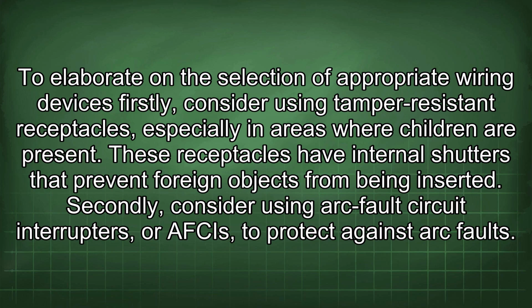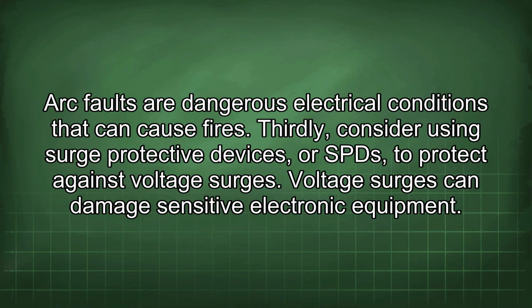To elaborate on the selection of appropriate wiring devices, firstly consider using tamper-resistant receptacles, especially in areas where children are present. These receptacles have internal shutters that prevent foreign objects from being inserted. Secondly, consider using arc fault circuit interrupters, or AFCIs, to protect against arc faults. Arc faults are dangerous electrical conditions that can cause fires. Thirdly, consider using surge protective devices, or SPDs, to protect against voltage surges. Voltage surges can damage sensitive electronic equipment.